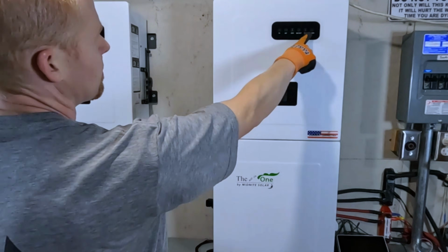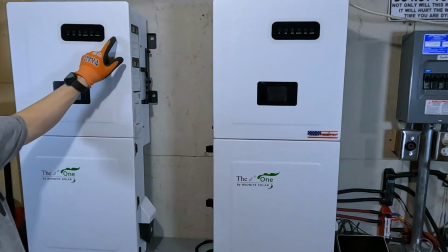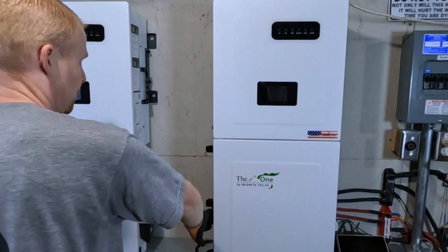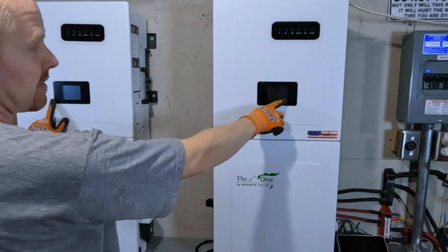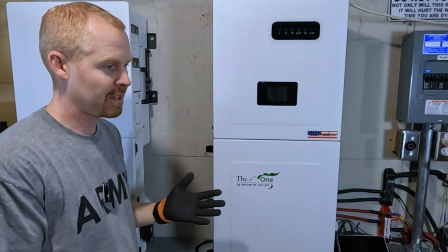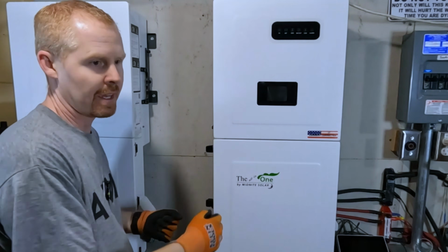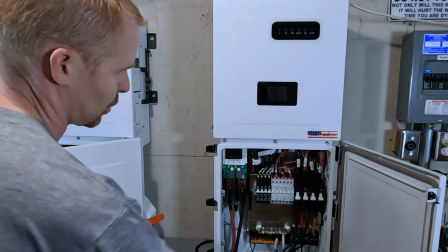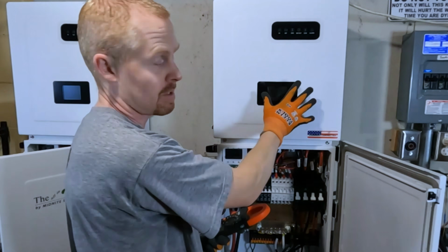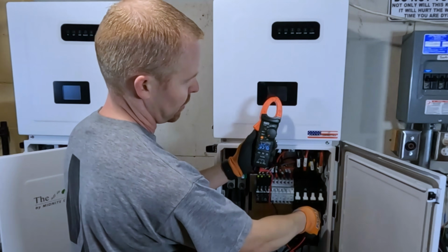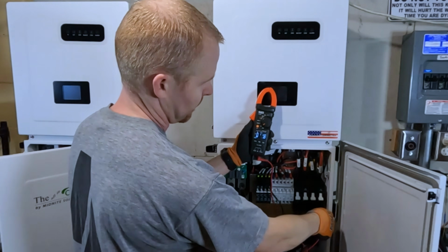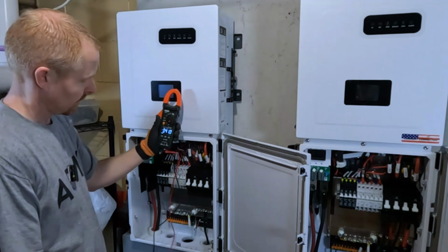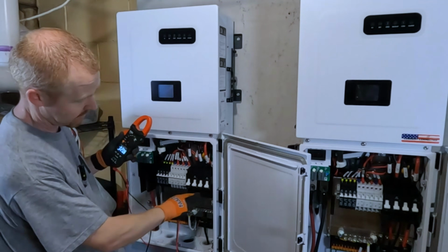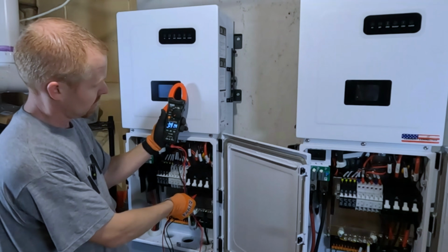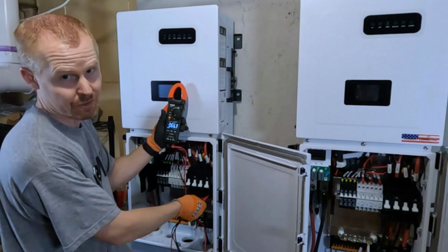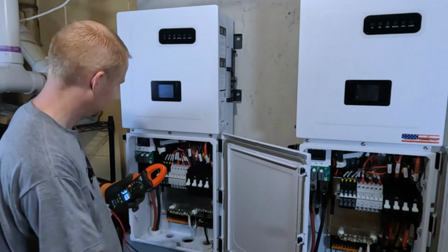So first thing, we can see that both inverters are turned off. We don't have any lights up here. If I press the buttons on the side, the displays don't light up. But just for peace of mind, we're going to check the AC connections to make sure that there's no power there. So I've got all the breakers turned off. This is my initial inverter. This is going to be the master inverter. So we'll check for output. No output. Check for input. No input. On the new inverter, we don't have anything connected, but I'm still going to check. No output. And obviously, no input because there's nothing there.